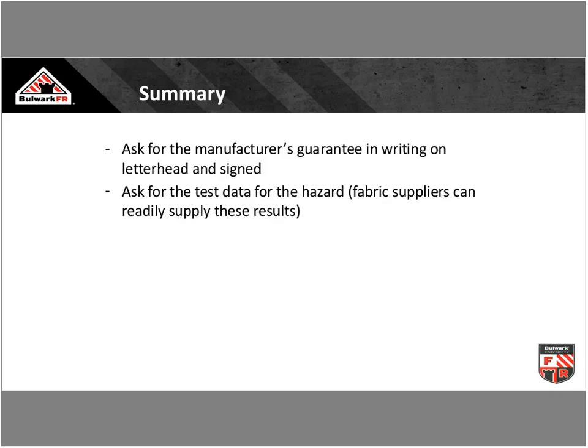When looking for folks, ask for the manufacturer's guarantee in writing on letterhead and get a signed copy of it. Make sure that guarantee is not tied to any standard, meaning it's guaranteed to meet ASTM whatever. Make sure it's guaranteed for life, that the garment is guaranteed to be flame resistant and arc rated for the life of that garment.